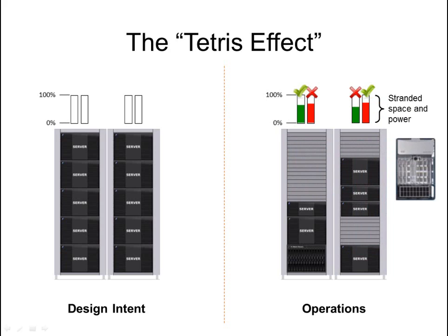In the typical enterprise, colo, or government data center, 30% or more of the IT resources will be stranded by the Tetris effect. And this is a huge waste of capital. But even worse than stranded capital is the fact that IT equipment is put at risk by resource fragmentation. So you can imagine this unit being installed and tripping a circuit breaker because the power distribution had become fragmented and unavailable to this particular deployment.